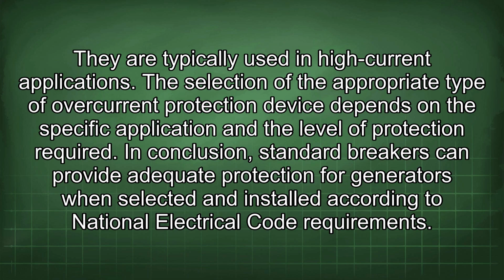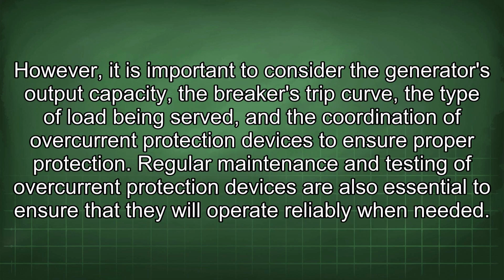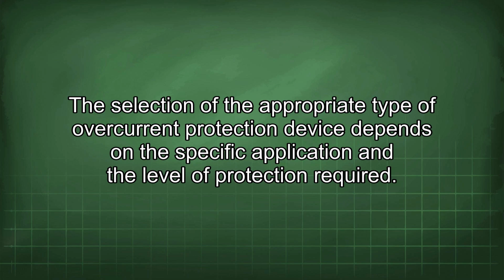In conclusion, standard breakers can provide adequate protection for generators when selected and installed according to National Electrical Code requirements. However, it is important to consider the generator's output capacity, the breaker's trip curve, the type of load being served, and the coordination of overcurrent protection devices to ensure proper protection. Regular maintenance and testing of overcurrent protection devices are also essential to ensure that they will operate reliably when needed. The selection of the appropriate type of overcurrent protection device depends on the specific application and the level of protection required.